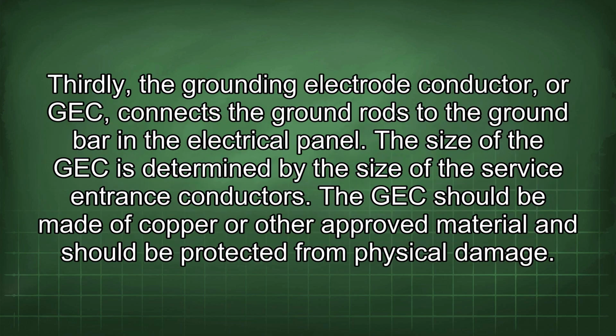Thirdly, the grounding electrode conductor, or GEC, connects the ground rods to the ground bar in the electrical panel. The size of the GEC is determined by the size of the service entrance conductors. The GEC should be made of copper or other approved material and should be protected from physical damage.